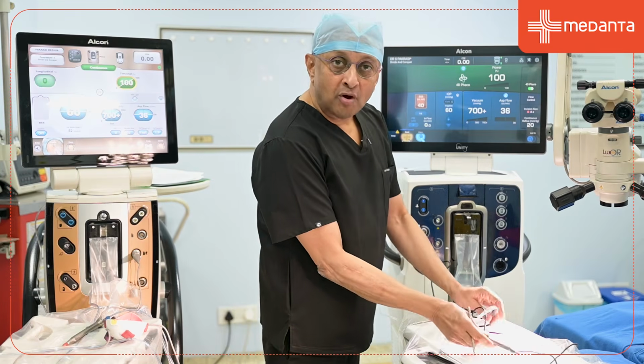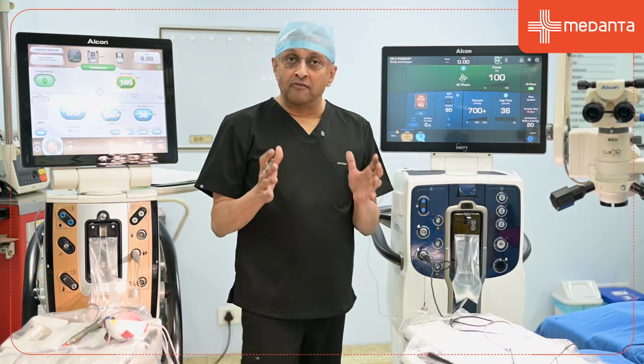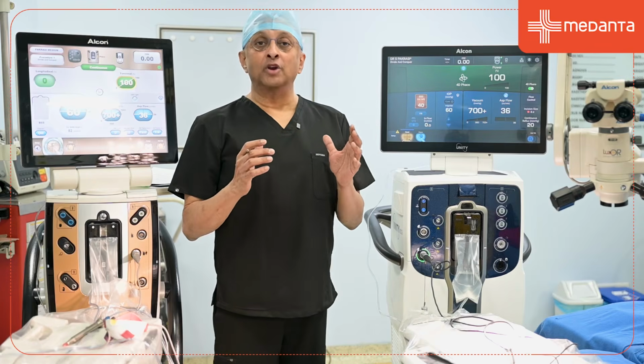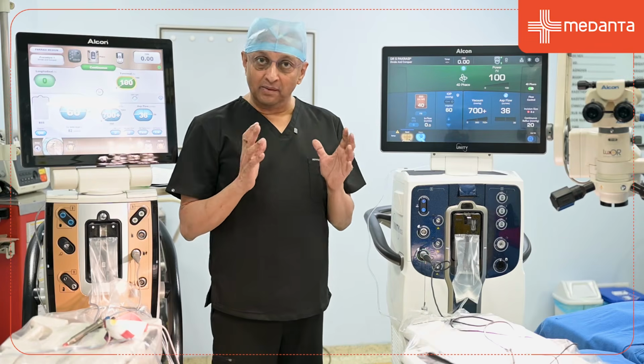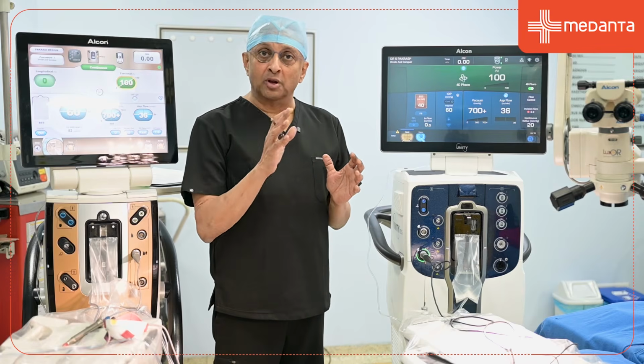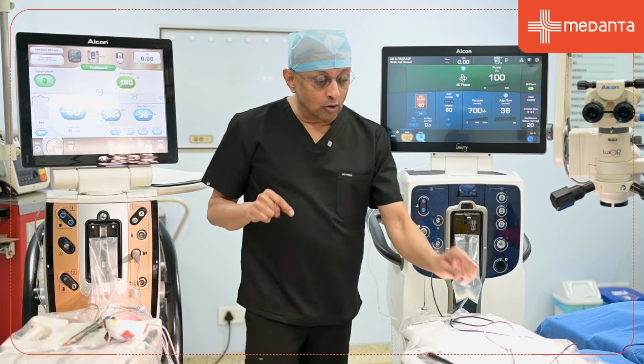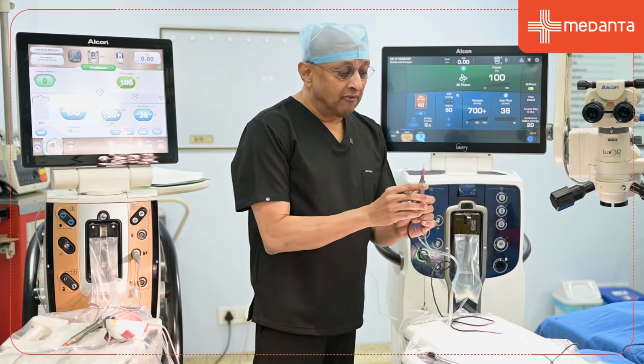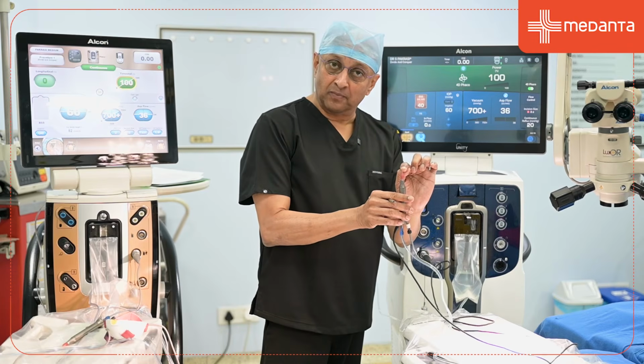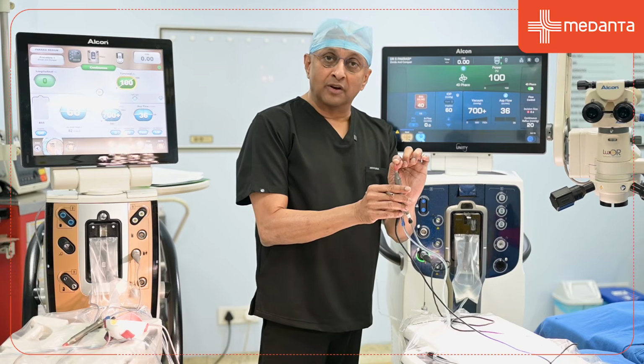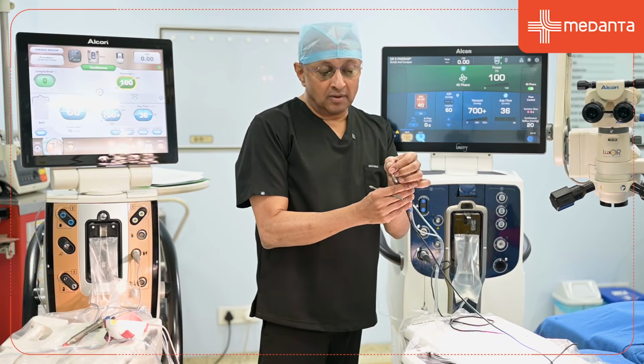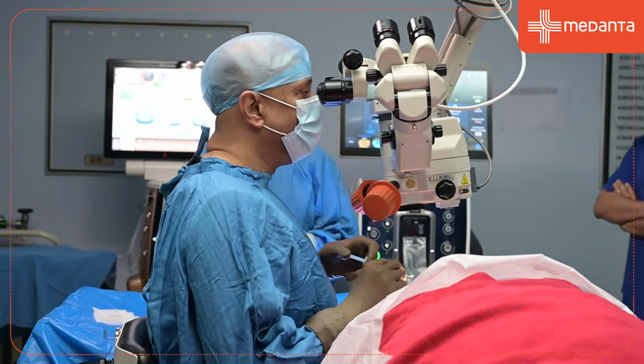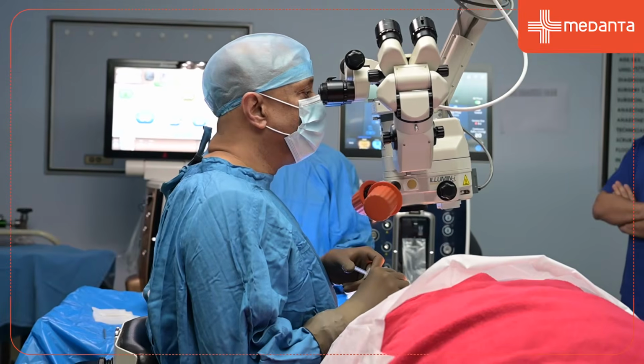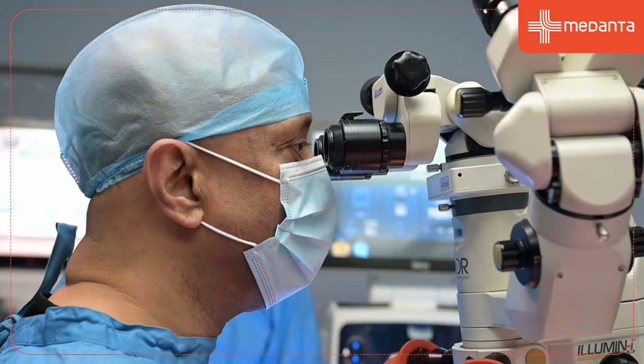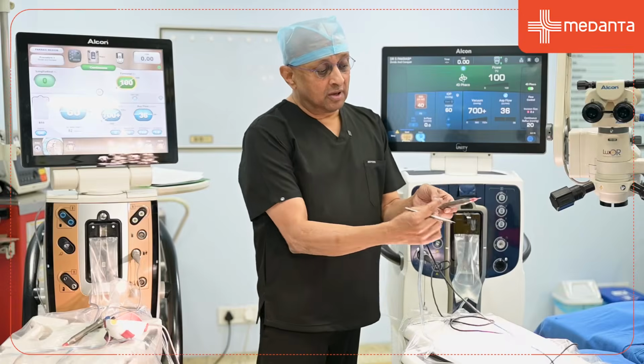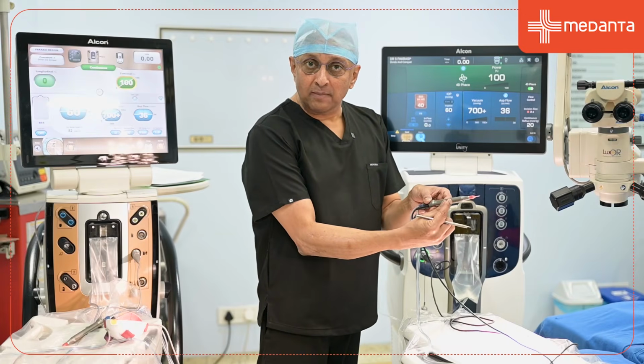So Phaco emulsification or 4D cataract surgery means a 3-dimensional movement of the tip of the Phaco probe, which is inside the eye, which you can see here right at the tip here. This is not even a 1 millimeter titanium probe, which is going to move in 360 degrees at 40,000 cycles a second with the crystal which is in the handpiece.